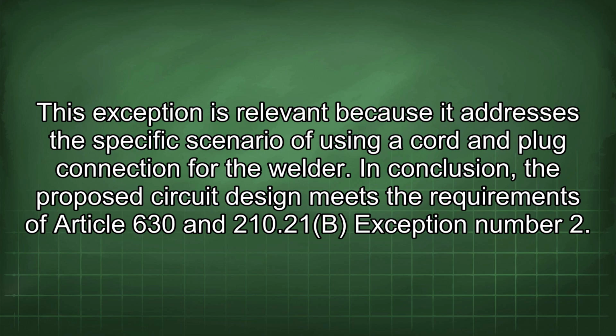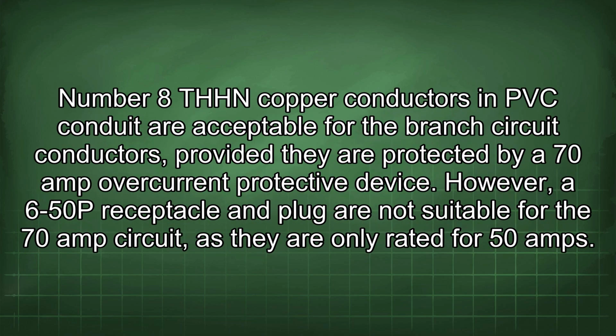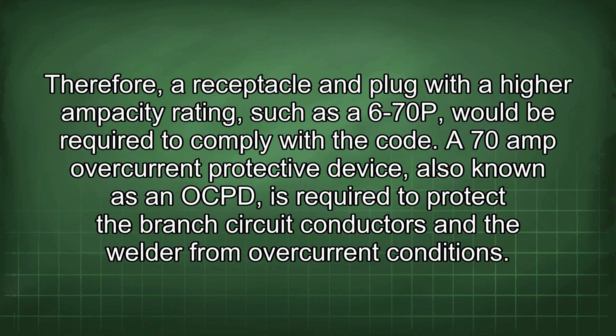In conclusion, the proposed circuit design meets the requirements of Article 630 and 210.21(B) exception number 2. Number 8 THHN copper conductors in PVC conduit are acceptable for the branch circuit conductors provided they are protected by a 70 amp overcurrent protective device. However, a 6-50P receptacle and plug are not suitable for the 70 amp circuit, as they are only rated for 50 amps. Therefore, a receptacle and plug with a higher ampacity rating, such as a 6-70P, would be required to comply with the code. A 70 amp overcurrent protective device, also known as an OCPD, is required to protect the branch circuit conductors and the welder from overcurrent conditions.